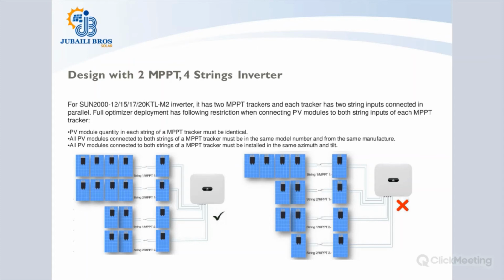The number of strings in an MPPT should not be different. Here we have 20 for the same MPPT. For a different MPPT, MPPT2, you can have, let's say, 17, and it is still recommended. What is not recommended from Huawei is this situation, where you have a different number of strings connecting to the same MPPT. In this case, let's say 20 and 17, or 17 and 15. It is not acceptable. This is the recommended case for this purpose.